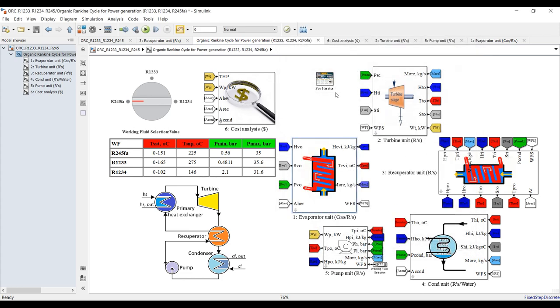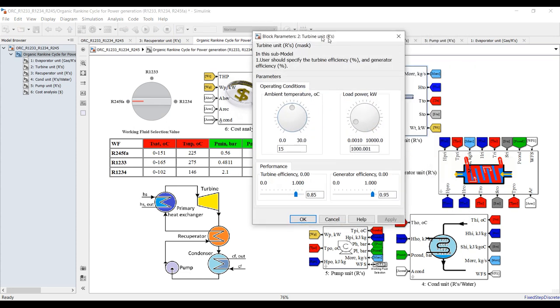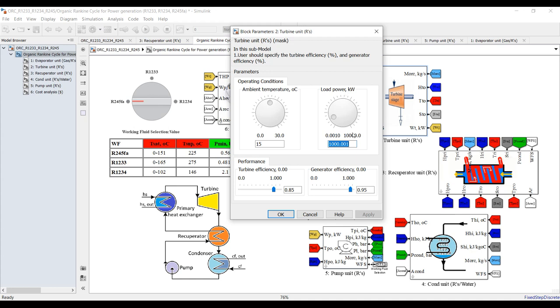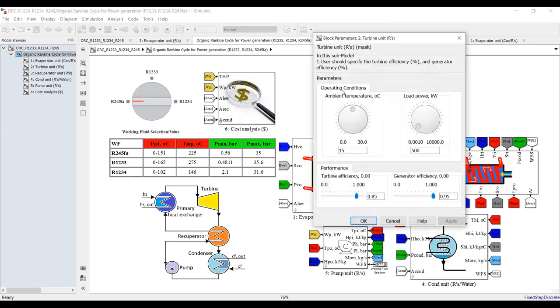For the turbine, the power determines your load. Suppose I need 500 kilowatts of power. Generator efficiency is 95%, turbine efficiency is normally around 0.85, and the reference ambient temperature is 15 degrees Celsius. This is your load control — very important, as the cycle tells you what the design aspects are under a specific load. I'm going with 500 kilowatt of power.